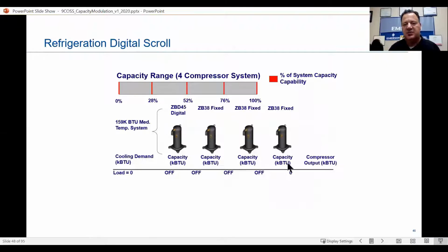So here's a nice application. Let's pretend this is in some type of a rack system. Let's say it's a supermarket and it's a holiday weekend and you're getting all your goods and what have you before the holidays. Down at the bottom, you can see the compressor. This is our digital, the lead compressor. The rest of these are all fixed compressors. Notice this is a ZBD 45 digital. These are 38 fixed, okay? So 159,000 BTUs, medium temp system. Here we go at the store, and the day starts to pick up, and we call for the first compressor to come on. Again, this is somewhere between 10 to 100% of its capacity.